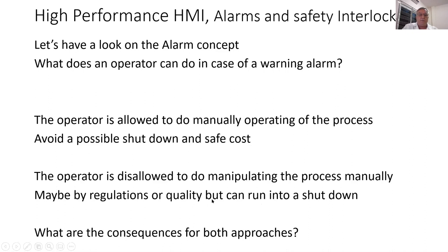If you don't give them some possibilities, they want to do some, and then they go in the field and then they manipulate a hand valve. So we don't have any connection to the DCS with a hand valve. A hand valve normally should be open or closed, but it should not be used for normal operating. But I have seen many times that it happened that the operator just goes shift by shift and just turns the hand valve. So I tuned a temperature control on a vessel, and it was really a very complicated and difficult to tune temperature control.